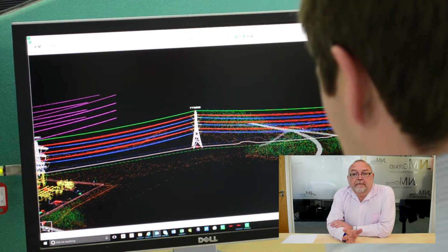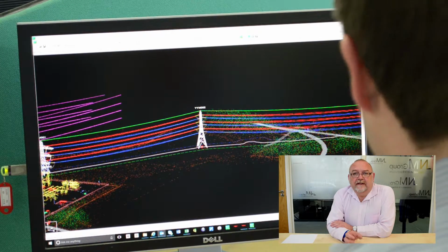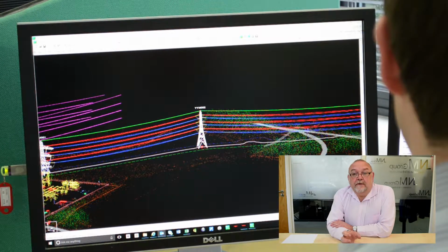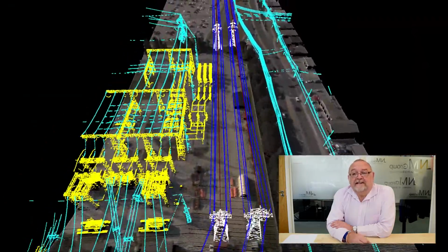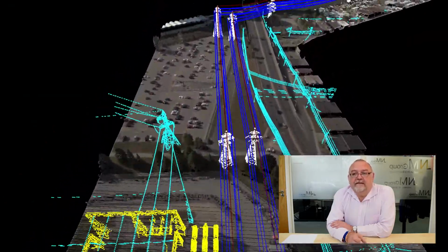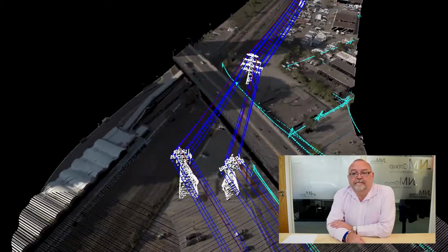The larger selection of conductor types and sizes, including HTLS, high temperature, low sag conductors. The availability of specialist engineering tools, such as PLS-CADD, which provide precise calculations of applied loadings and available structure capacities using these probabilistic design codes. And the availability of LiDAR datasets to populate these engineering tools and allow exact calculation of structure loadings and capacities.